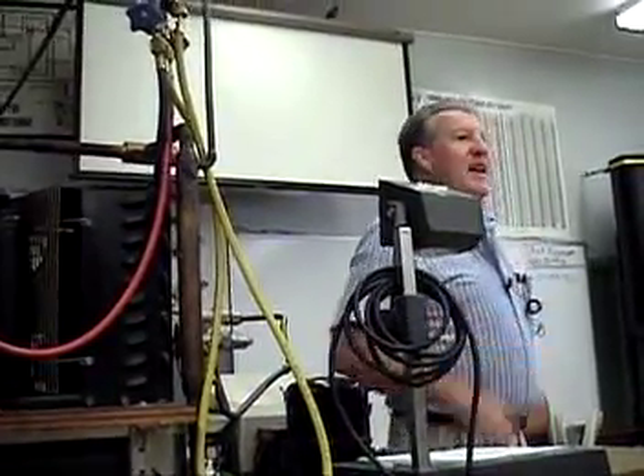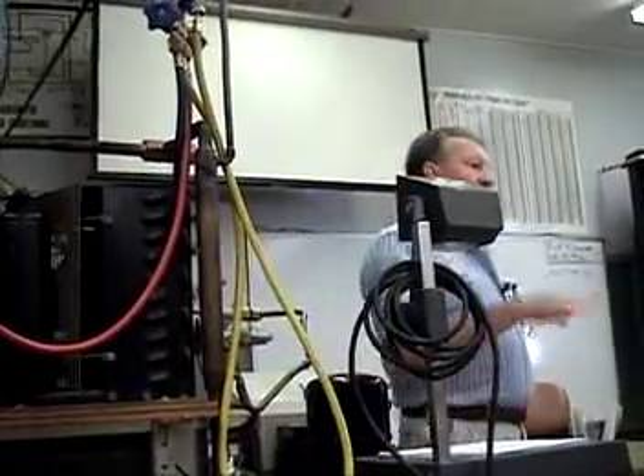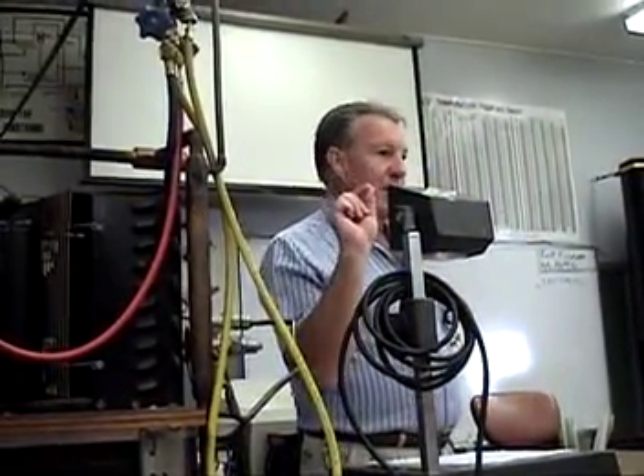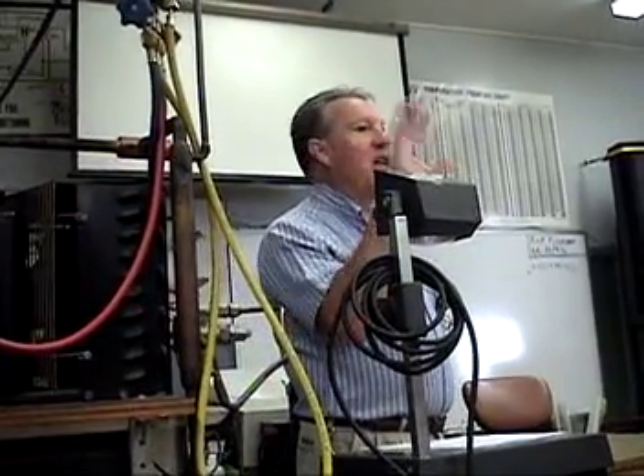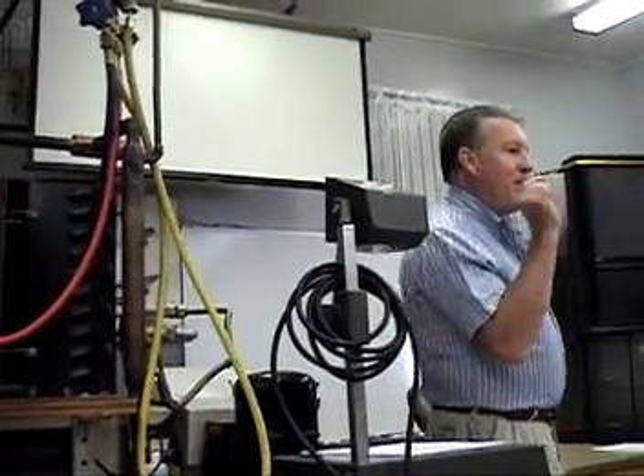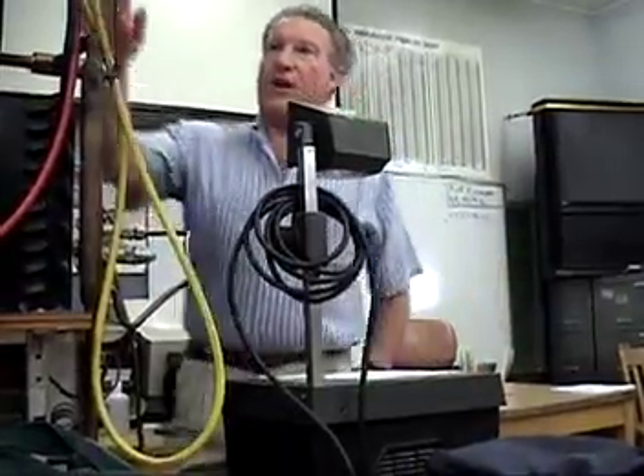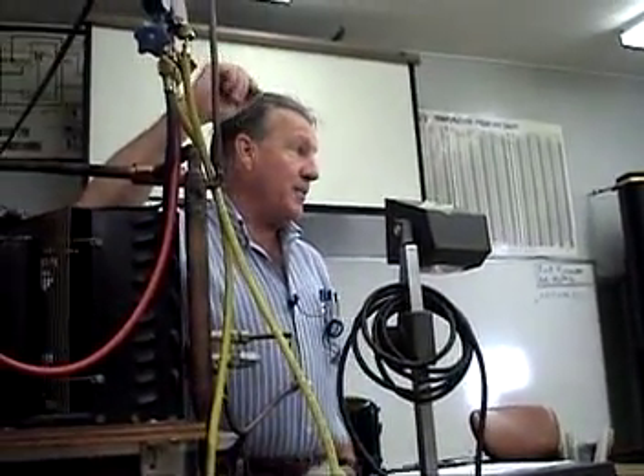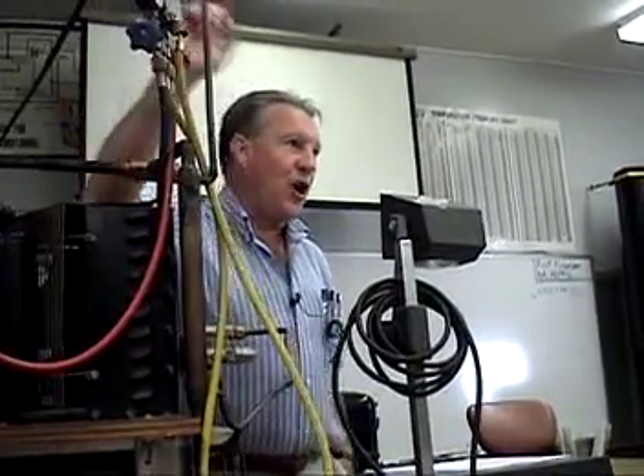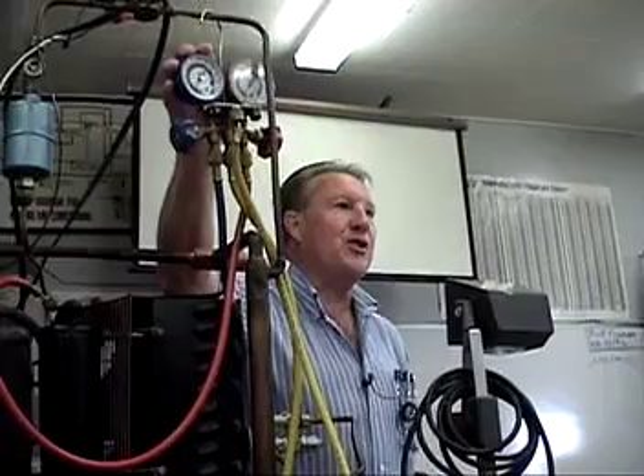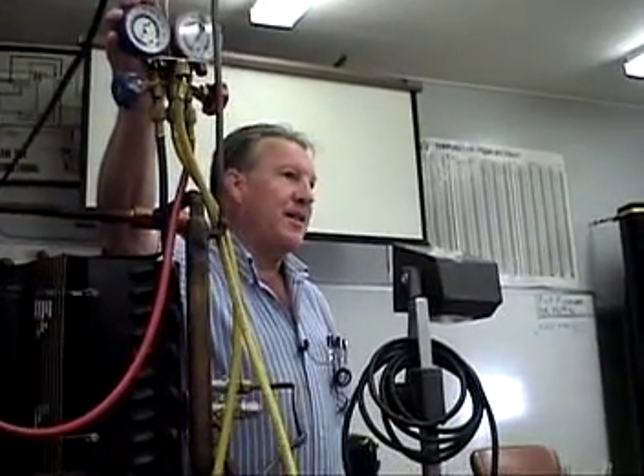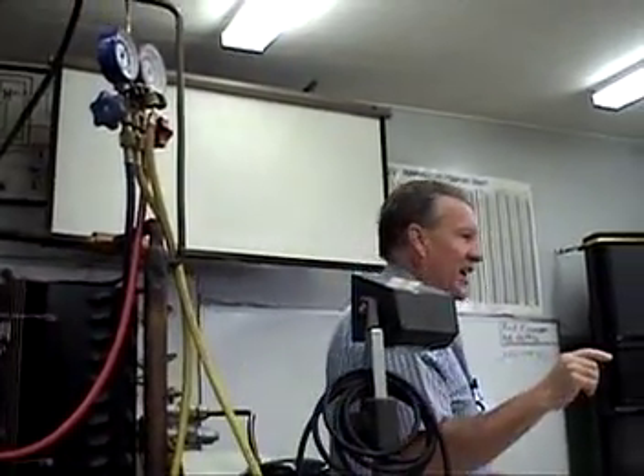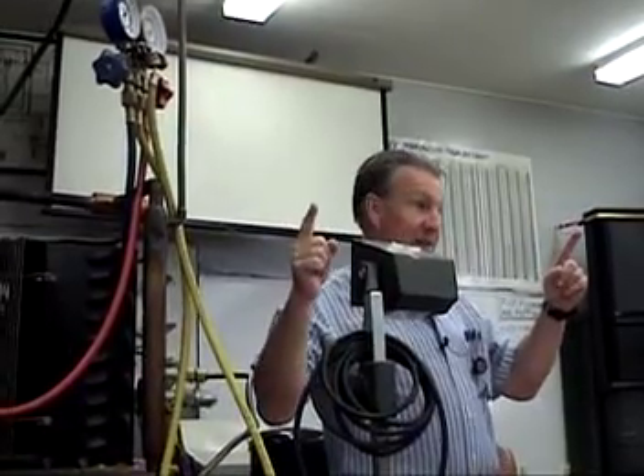The gurgling thing is in fact a restriction. Now, why are you seeing a little bit of frost where it goes into the evaporator? Flash gas. It's metering in, but it's not metering in fast enough for the pressure on the low side to be up where it belongs. It's starving the evaporator. When you starve the evaporator, what happens to the low side pressure? Up or down? Down. When the low side pressure goes down, what does the temperature of the refrigerant do? Goes down. That's why you have frosting. But there's just a little bit of frosting, so that would tell you that it was a restriction. That's where I would hang my hat.